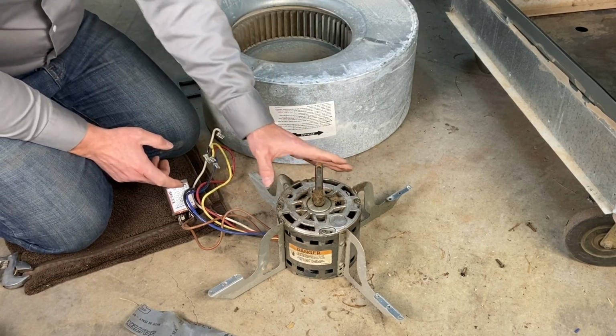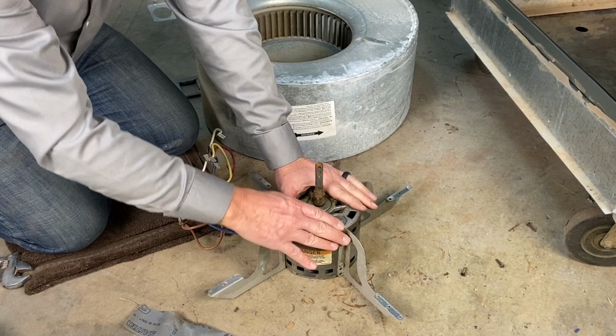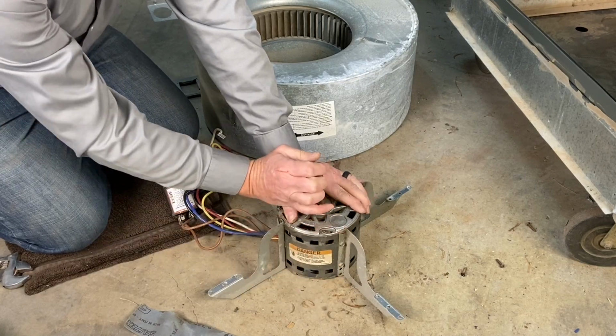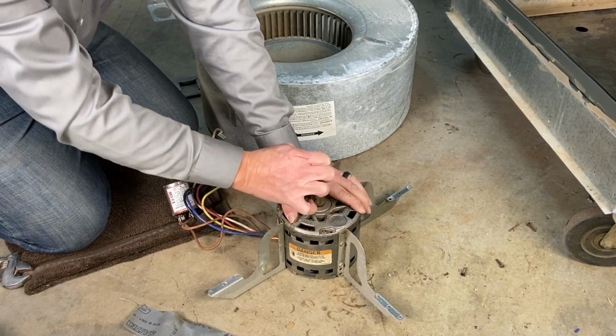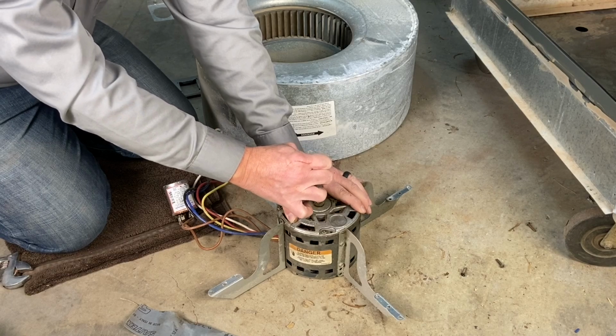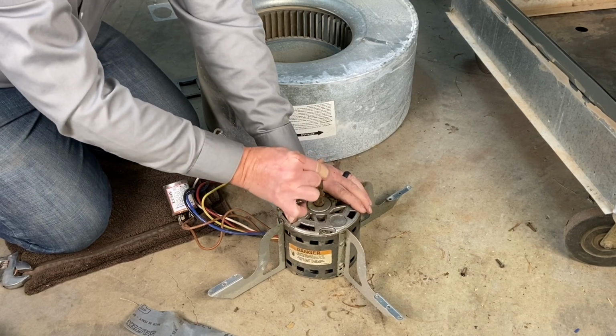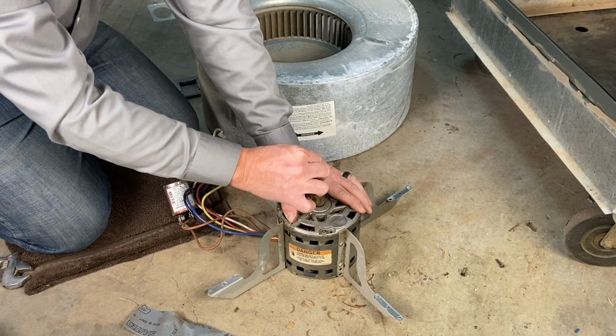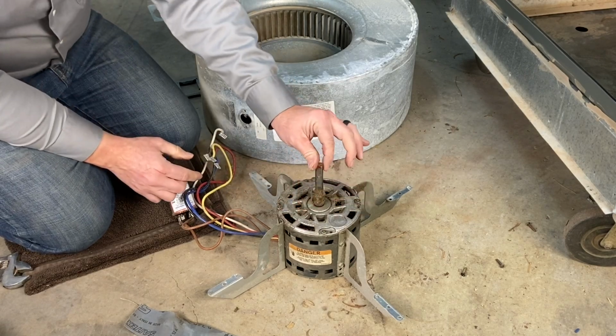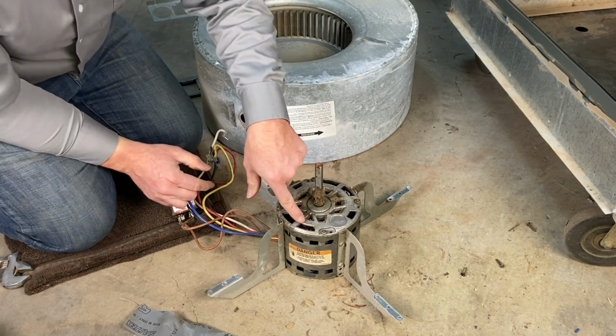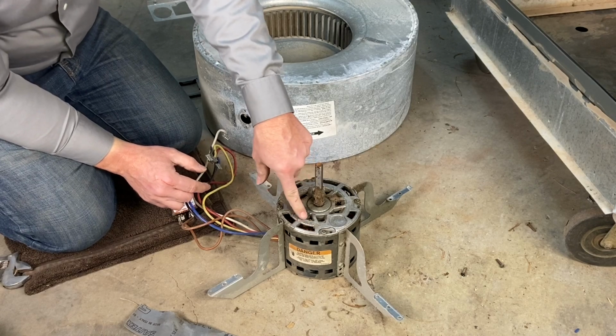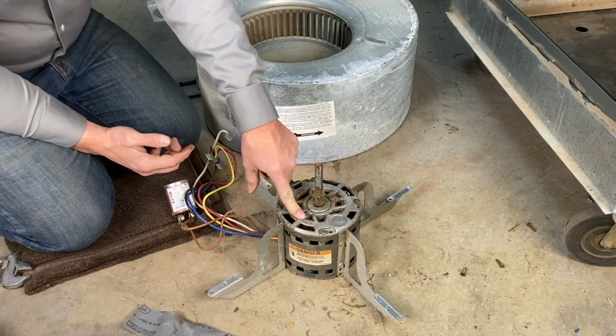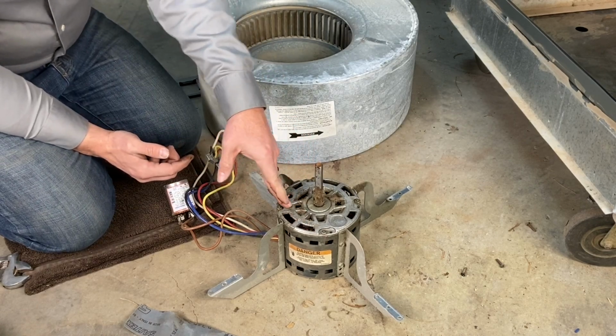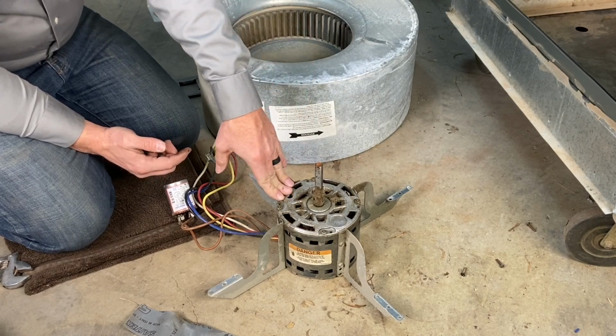So what I want to do is check the motor bearings. I'm going to hold the motor flat on the ground, and what I do is move the shaft back and forth. And I don't feel any play in the bearings, which is good. Up and down, you will have play, but we don't care about that. We're looking for back and forth. So this motor, the bearings are good. Now I want to look at the windings. I want to look in there and see if that copper looks discolored. A lot of times if you have discolored copper, it's an issue where the motor's been overheating.